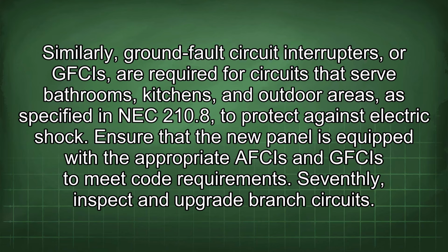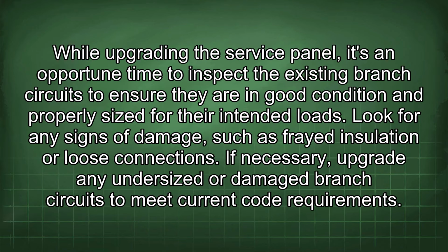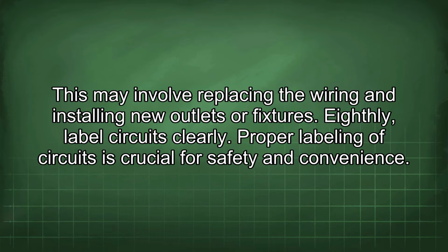Seventhly, inspect and upgrade branch circuits. While upgrading the service panel, it's an opportune time to inspect the existing branch circuits to ensure they are in good condition and properly sized for their intended loads. Look for any signs of damage, such as frayed insulation or loose connections. If necessary, upgrade any undersized or damaged branch circuits to meet current code requirements. This may involve replacing the wiring and installing new outlets or fixtures.